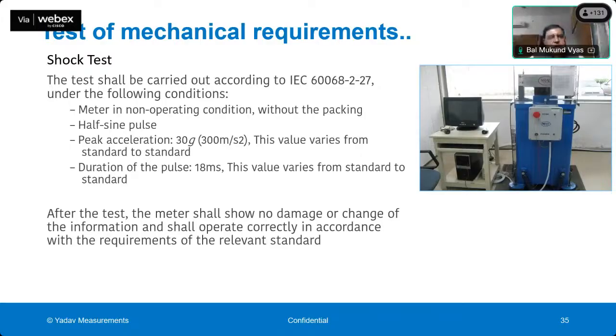Typically, the shock level is 30 G. 30 G means 30 times the gravitational acceleration, which is 300 meter per second square. So the meter is subjected to the shock with a duration of 18 milliseconds, and the shock is applied in different axes. And then the meter is checked for accuracy and its performance, that it should not show any damage or change in information. It should give us the correct reading.